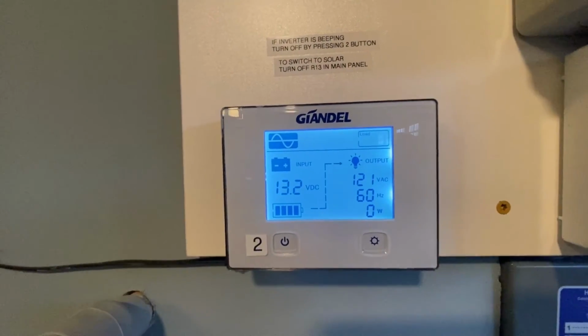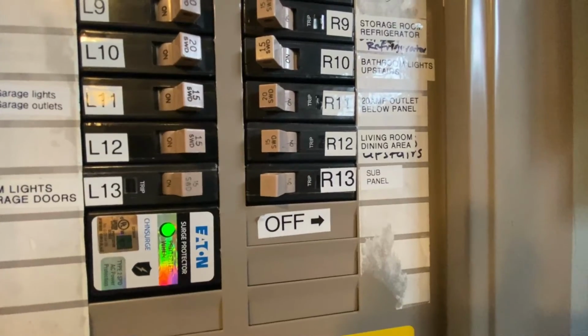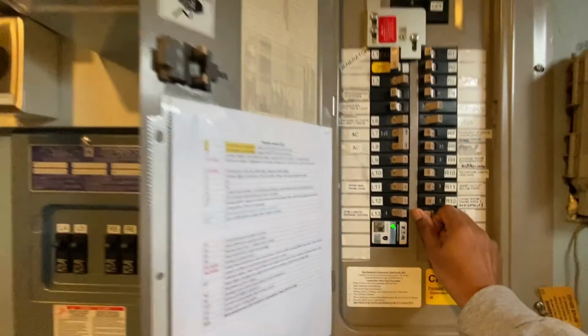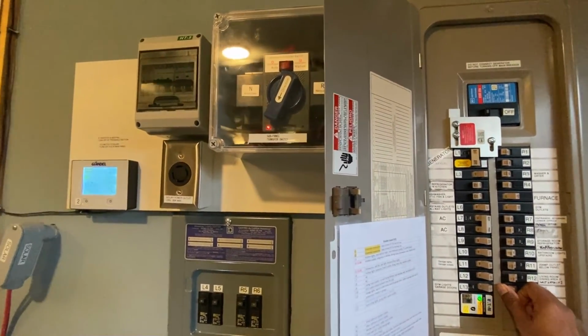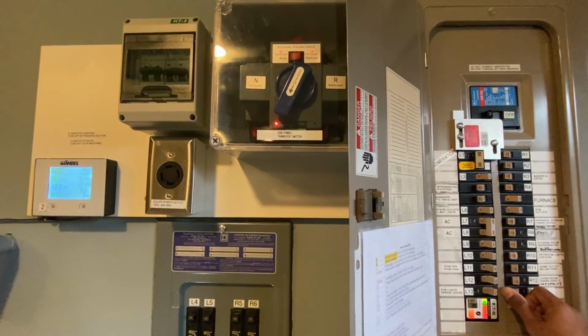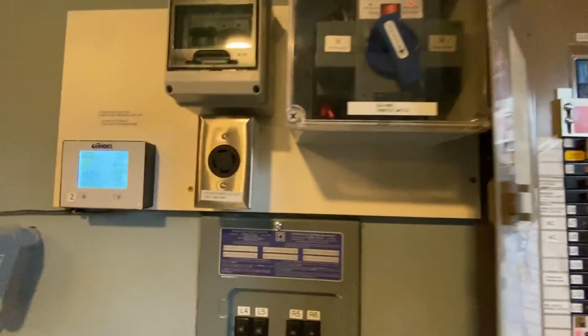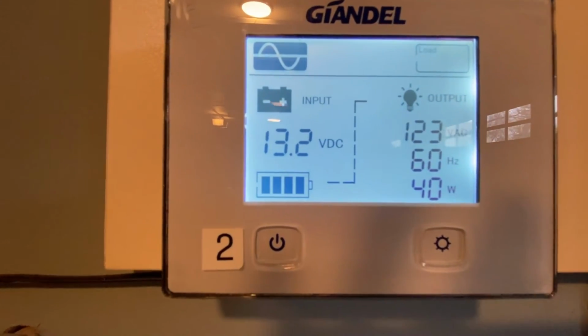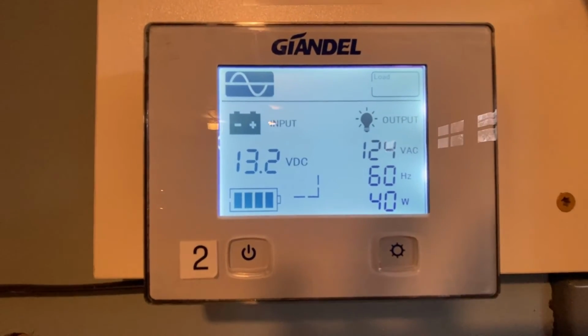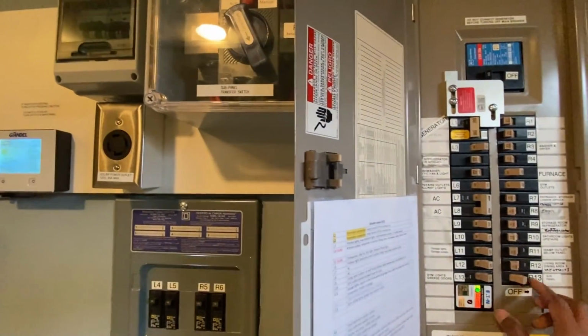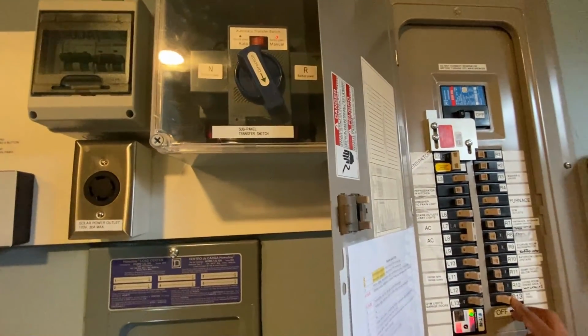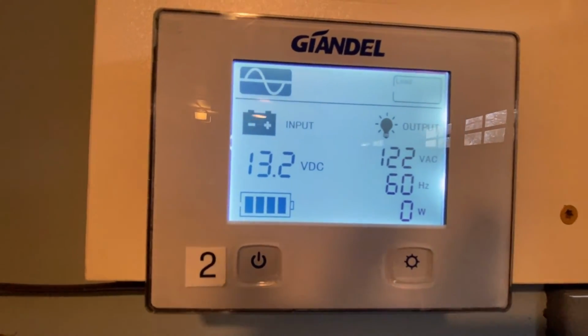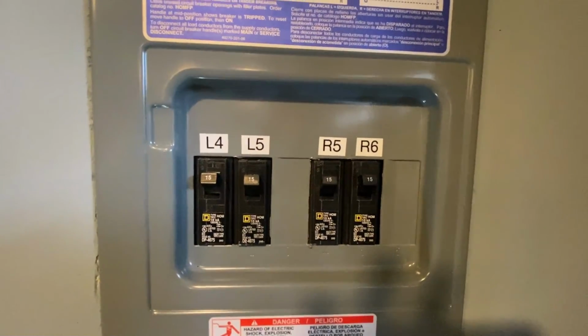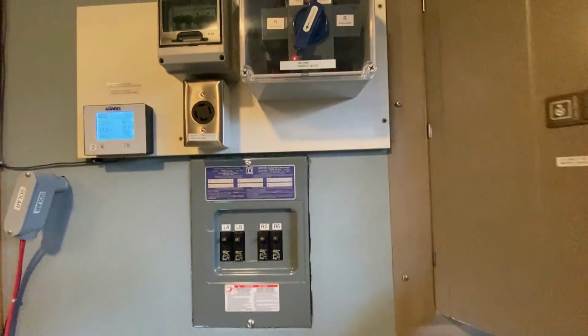So here is the distance between that battery storage station and this panel right next to the breaker panel of the house. I have this single 50 amp breaker feeding the 4 circuits of the sub panel. So when I turn that off, when the inverter power is on, the transfer switch automatically switches to solar power. Now you can see the small wattage 40 watts displaying on that panel because something is drawing a small amount of current. When I turn on the main power using that breaker, the transfer switch turns off the solar power to the 4 circuits I have selected here. So that's basically how the system works.